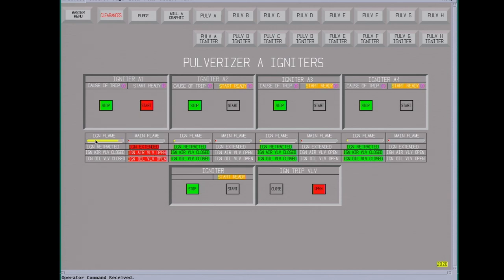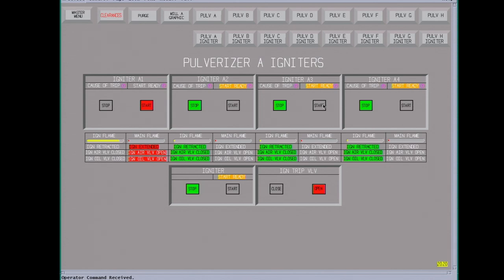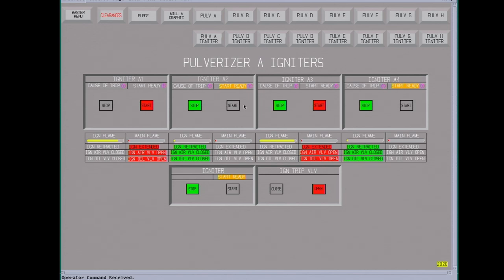This yellow line means that it is showing we have a flame on it. The flame scanners use ultraviolet light. You can't use infrared, there's too much infrared. So when fuel burns it gives us an ultraviolet signature. We have to have the igniters running, at least one running, before 10 minutes or the boiler will trip. It voids the purge. These are required for lighting off the coal, main burners also.